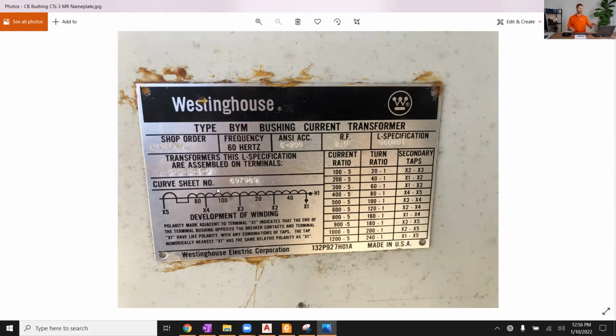Inside the breaker cabinet, a lot of times we have a nameplate that shows the different CT taps. This is a multi-ratio CT, and so we can tap it down to a smaller ratio if we need to for a particular application. It's desirable, if at all possible, to keep them at full tap, which makes you less likely to saturate your CT, but sometimes you don't have an option. You have to tap it down. You have to make sure you derate that CT if that's your situation. Again, kind of beyond this course, but just making you aware that with multi-ratio CTs, we have multiple taps.